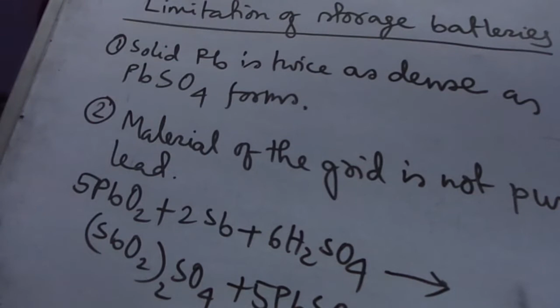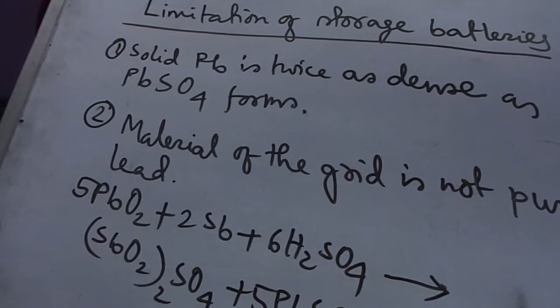Another one is that batteries are for stationary applications. Photovoltaic lighting systems can use Sb-free plates. An ordinary battery cannot be allowed to discharge more than about 50% of its stored energy. Such a discharge is known as deep discharge. Sometimes it may not be possible to recharge or revive the battery after a deep discharge. If the discharge reaction is allowed to go to completion, all the lead may be consumed and there would be no electrode left.